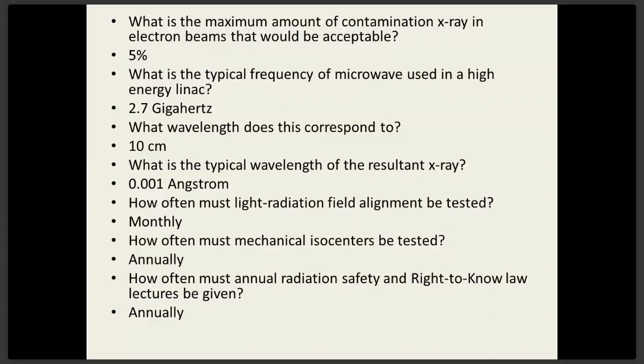Light radiation field alignment must be tested monthly by the physicist. Sometimes therapists test them weekly or monthly. If the physicist asks them really nicely, sometimes the therapist will test light field, radiation field for them. But TG40 says it has to be done monthly, so that usually means the physicist. Mechanical isocenters are tested annually. Now, I know a lot of this gets tested daily, but the requirement is just annually on mechanical isocenters. And right to know law lectures have to be given annually. And I think that finishes the lecture.